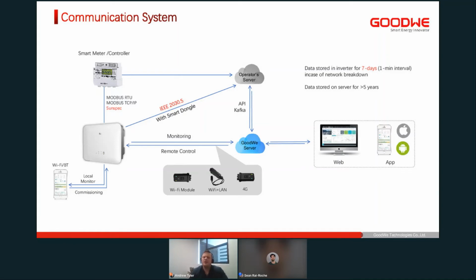And then just the general view on the data storage from our product. So the actual inverter stores data for up to 7 days in case of a network breakdown. So typically, if a system loses Wi-Fi or maybe the Wi-Fi router runs out of data, when the inverter does reconnect to the internet, it would upload that data. So it's quite nice because you don't want to lose the data just because of a network connection that was down. And then our data is stored on our server for up to 5 years. With the standard warranty of 5 years on our hybrid inverters, that's the reason for storing it for up to 5 years, so that there is some historic data in the event that you need to view that.